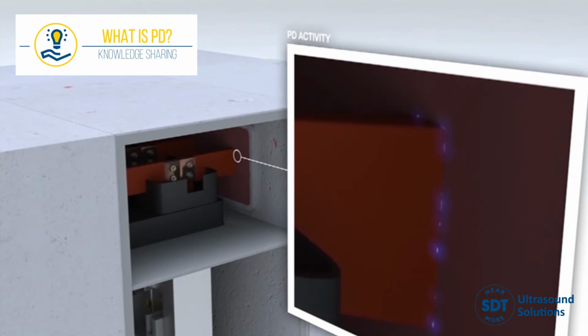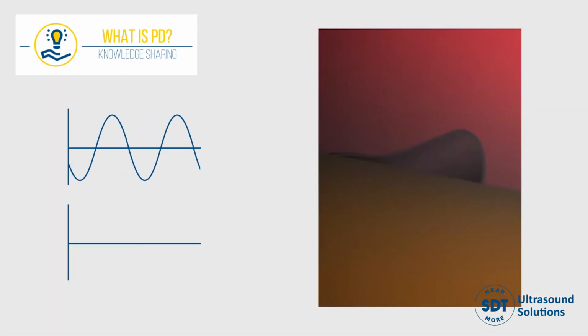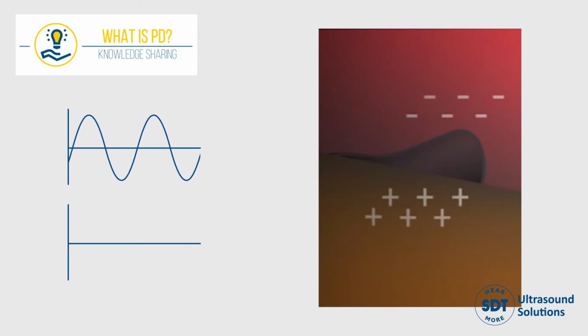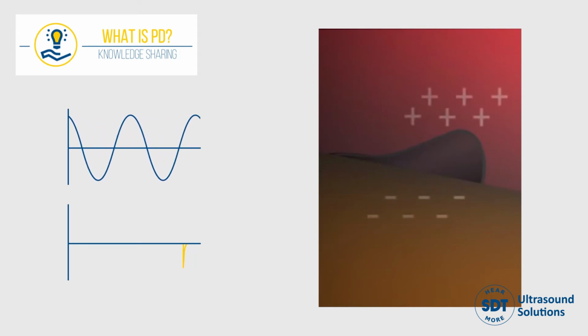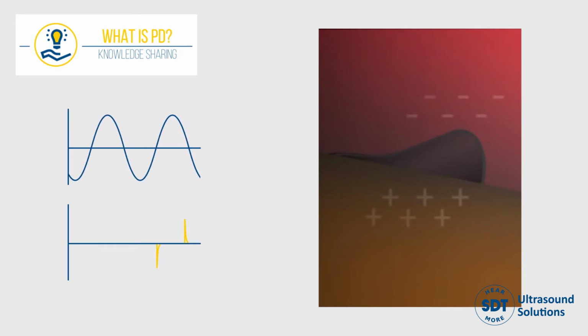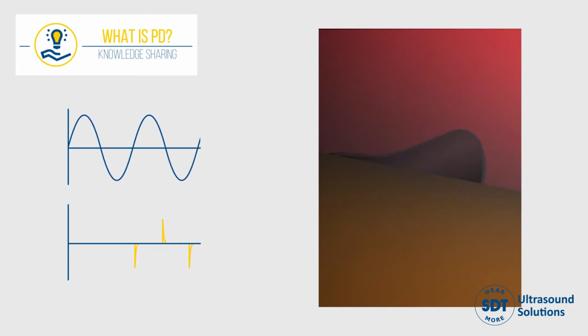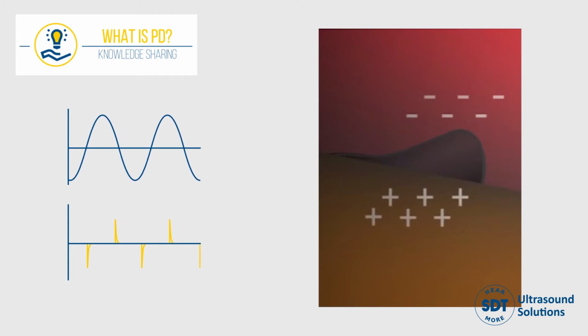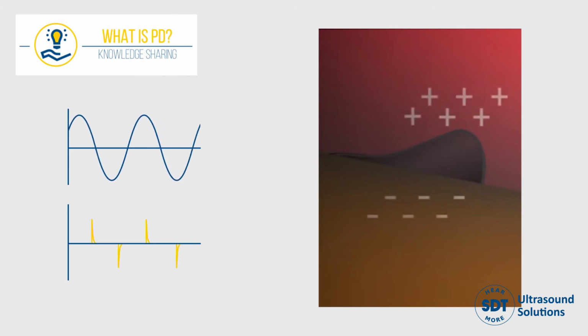But what is partial discharge? Well, partial discharge is a localized electrical discharge or a spark in an insulation system that doesn't completely bridge the gap between two conducting electrodes. It can occur at any point in the insulation system where the electric field strength exceeds the breakdown strength of that portion of the insulating material.